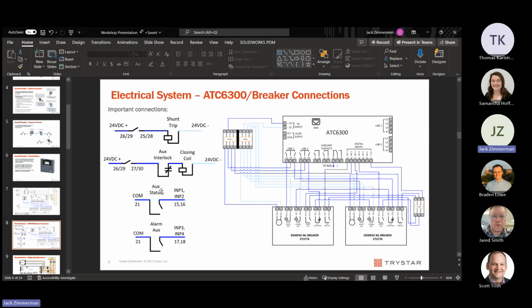That's it. So with this, are we able to outfit the breaker with other alarm functionality? That's a great question. Now you're going to say, so we have full control over the digital inputs and full control over whatever kind of alarms we want to go off the WL breaker. So we can program our own alarms into the ETU and into the breaker and do any alarm indication. It could be phase rotation. We could get rid of the phase rotation monitors and do phase rotation in the breaker, do alarms for that. I mean, yeah, there's a lot of capability there.